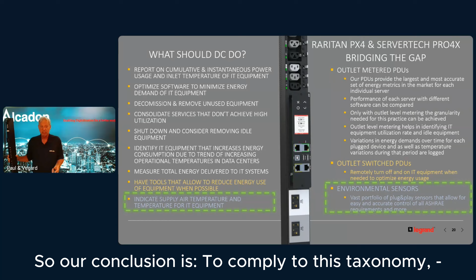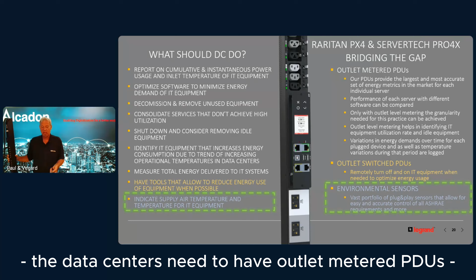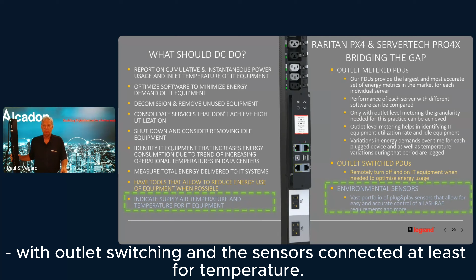So our conclusion is to comply with this taxonomy. The data centers need to have outlet metered PDUs with outlet switching, with the sensors connected, at least for temperature. What we see in the market, this Omdia chart, is showing the same trend: the fastest growing market in the intelligent PDU business is in this segment, outlet metered, outlet switched PDUs. It's up to 13 to 40% that we see this market.